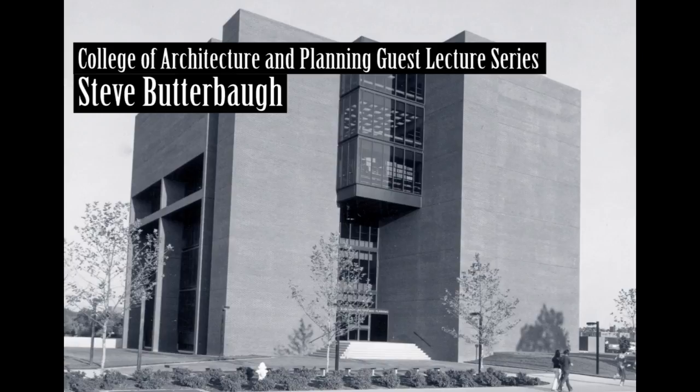The process of proposing changes means the specification of the nature and extent of the change. If thermal pane windows are to replace single pane windows, it means drawing enough details to see what kind of window will work and to show how the building skin is different. It means knowing the square footage of building skin that is to be changed to the new, lower U value and knowing what the change in U value is.